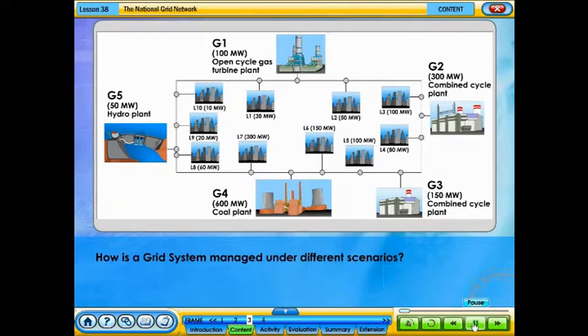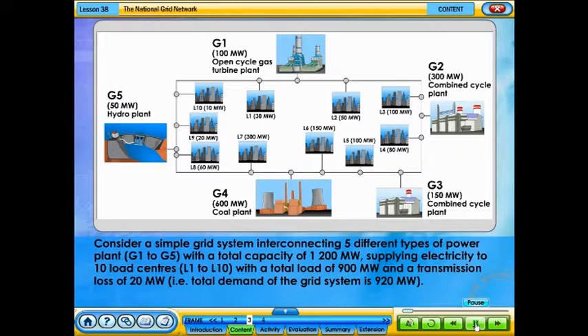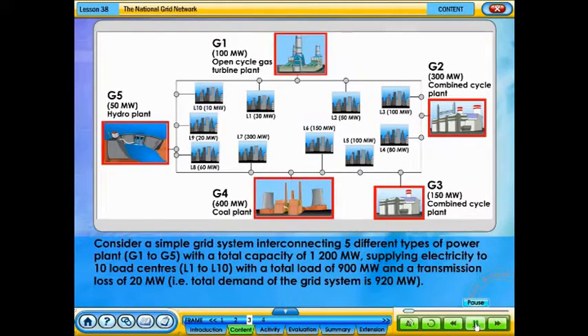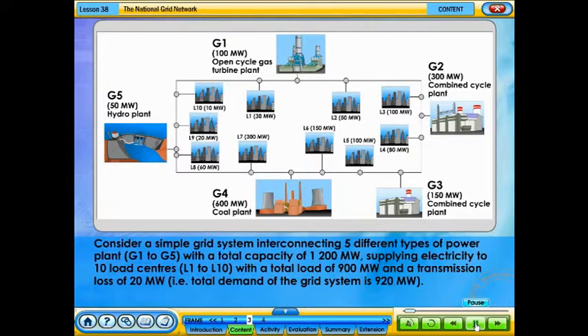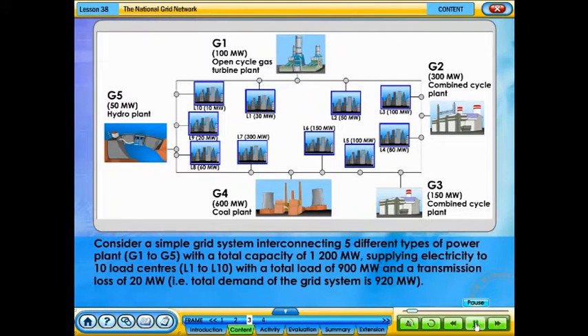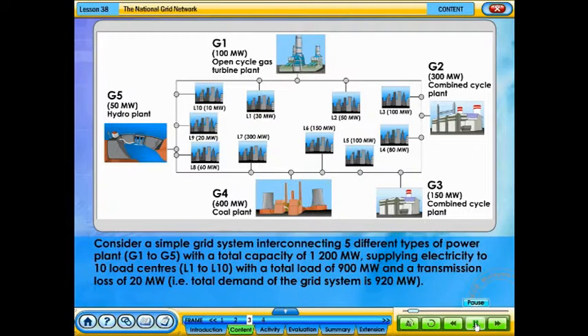The graphic shows the simulation of how a grid system is managed under different scenarios. Consider a simple grid system interconnecting 5 different types of power plant with a total capacity of 1,200 megawatts, supplying electricity to 10 load centers with a total load of 900 megawatts and a transmission loss of 20 megawatts. That is, the total demand of the grid system is 920 megawatts.